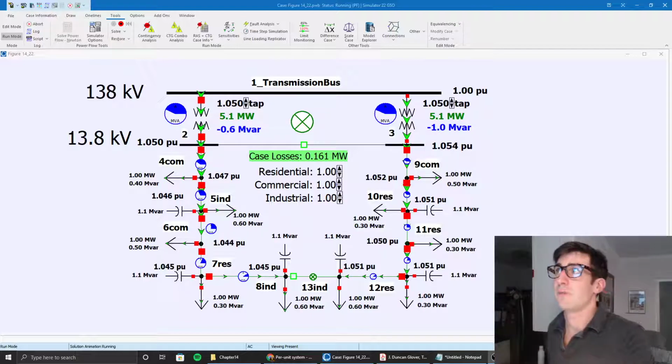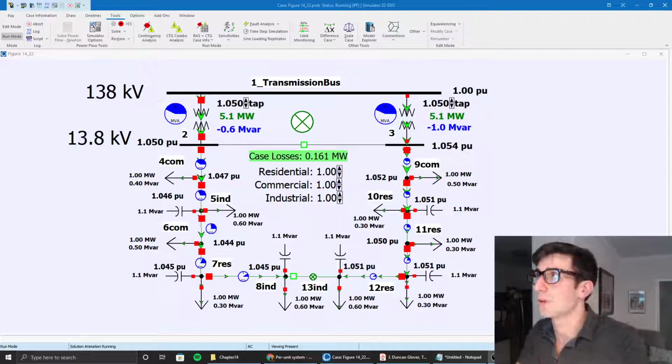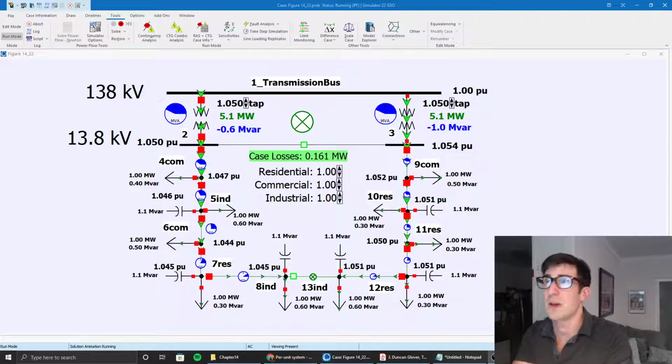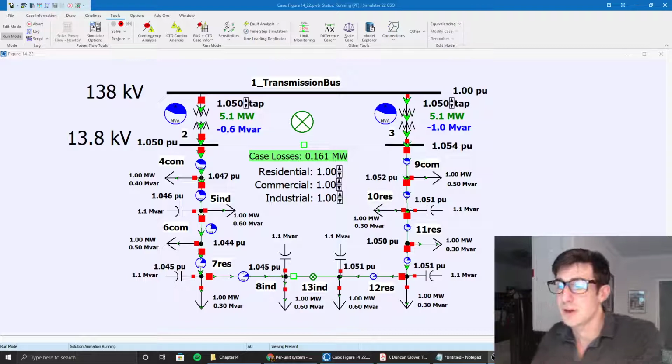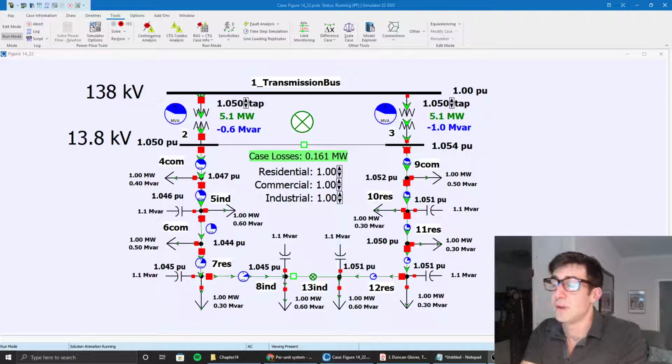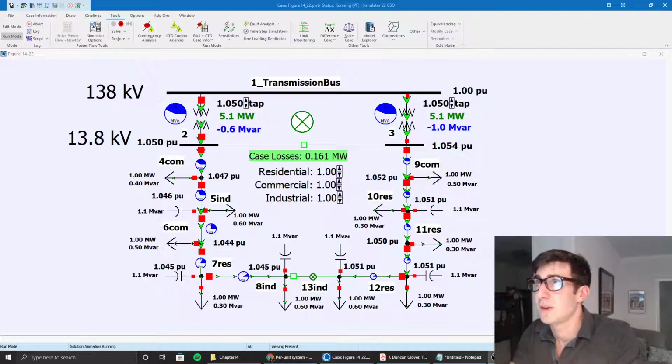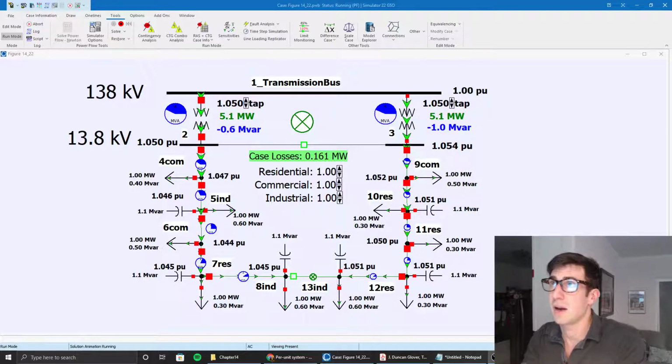First and foremost, a little background on this particular primary distribution system. It is interesting to note that a loop system is not the most commonly seen because it's not the most cost effective and low cost option. In low density demand areas, such as very rural areas, you will see a radial system. However, this is more reliable because you can sectionalize faults and isolate them so that they can be serviced and repaired.